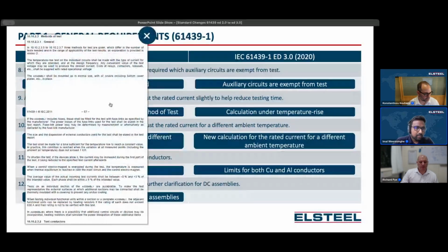Yes, under the method of testing, you don't see any calculation method in here, just to find out how much current that breaker or the bus bars or that component will take, because this temperature rise testing will last longer, more than 6 hours, between 6 to 8 hours. So we were unable to find out what would be the specific current which will stay within the limit.